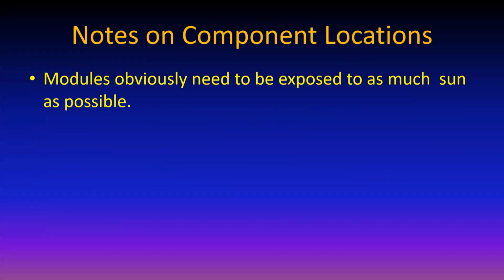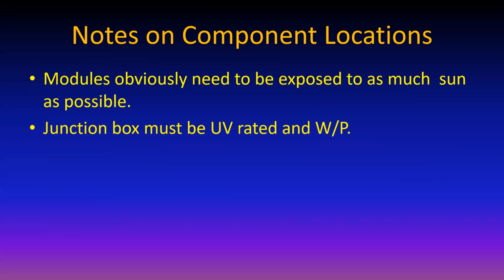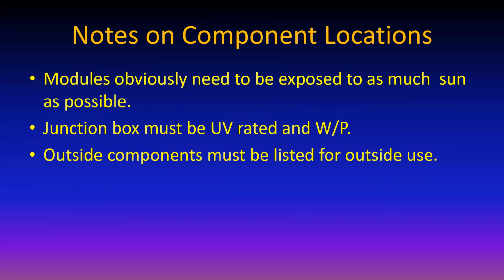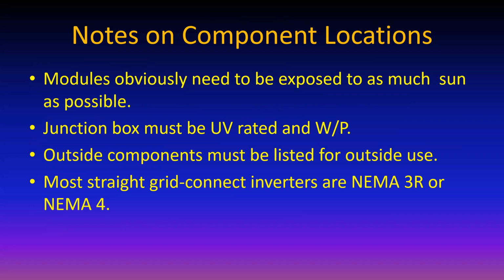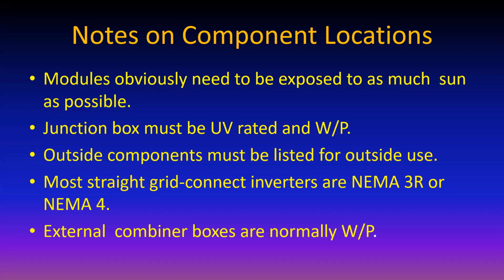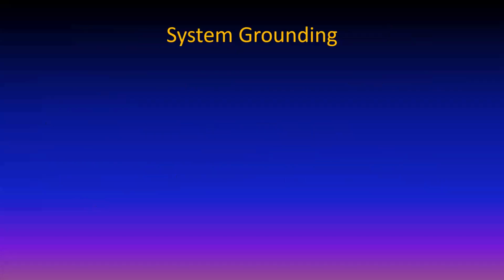Okay, component locations, modules, obviously they're exposed to the sun. Junction box has to have a UV rating and be weatherproof, at least a NEMA 3R, and oftentimes NEMA 4. And outside components, outside use. Most inverters are listed for outside use if they are straight grid connect. The battery backup inverters generally are not listed for outside use, but we're not doing those in this particular session. Combiner boxes, of course, obviously need to be weatherproof.